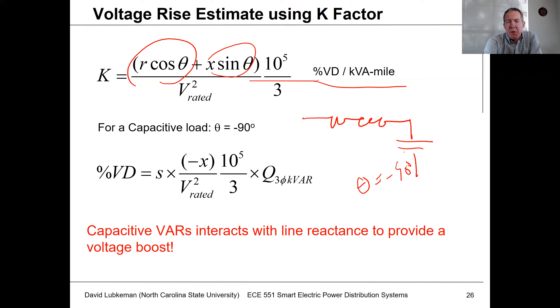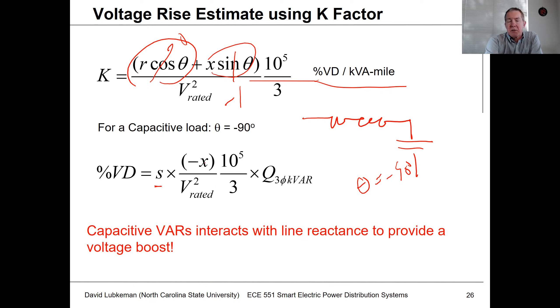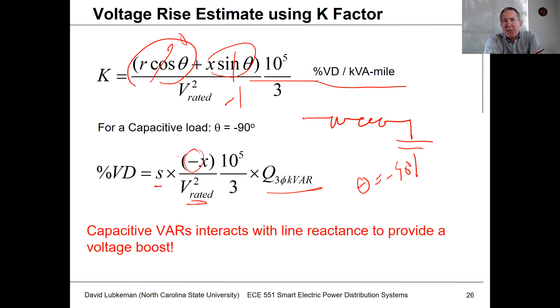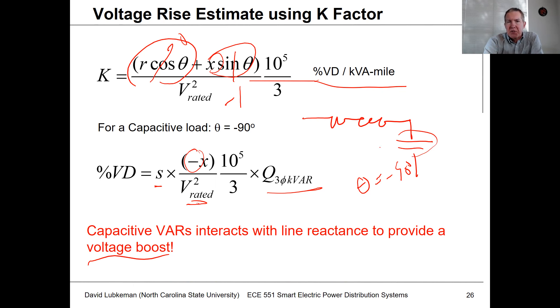If I substitute theta equal to minus 90 degrees into the equation, cosine of minus 90 degrees is simply zero, and sine of minus 90 degrees goes to minus one. So when I compute my voltage change, this is going to be the line length times minus the line reactance divided by the voltage squared — this is a line-to-neutral value — times 10 to the fifth divided by three, times whatever the capacitor value is in terms of kVAR. The interpretation is that a negative percent voltage drop term means instead of a voltage drop, we get a voltage boost. It's the interaction between the line reactance and the capacitance that gives us this voltage boost effect.